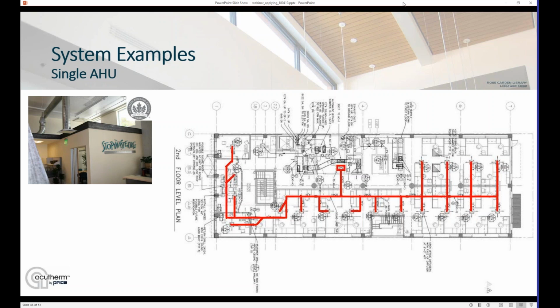And the decision was made early on to add better insulation to the building, better glass, better roof insulation. And they did it such that when combined with the zones of control provided by the Therma-Fuser Diffuser, they could treat this building as a single zone, even though there are multiple exposures on it. So a combination of good insulation and the subzoning of the Therma-Fuser diffusers allowed this to happen.